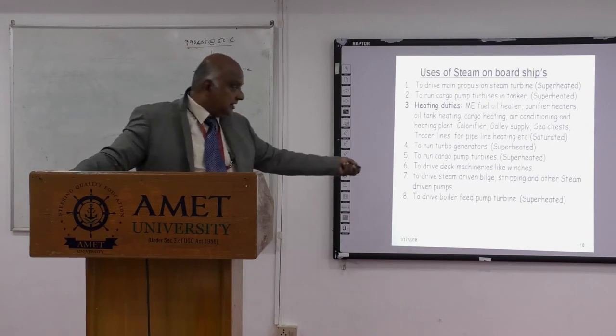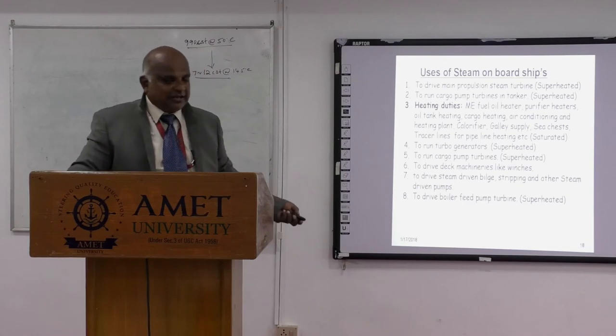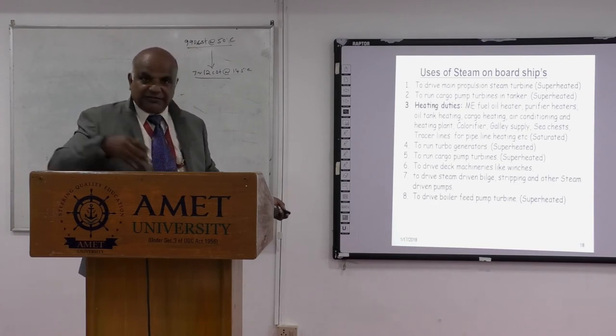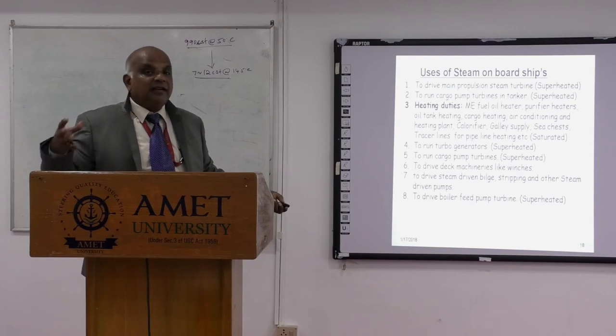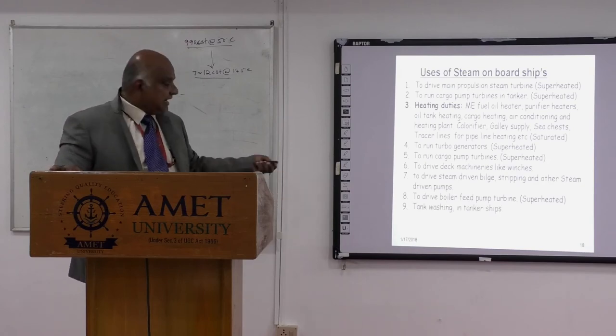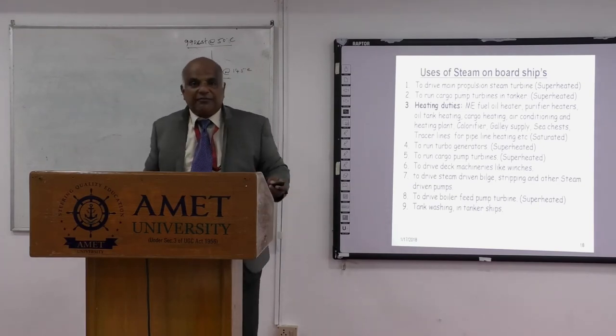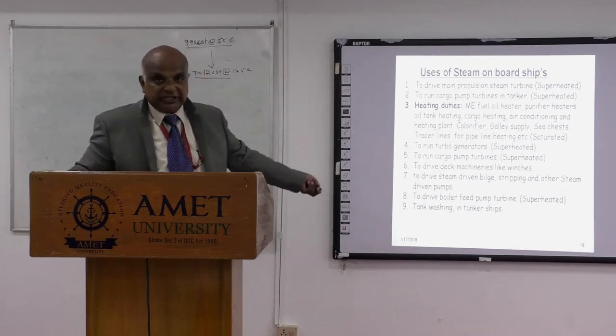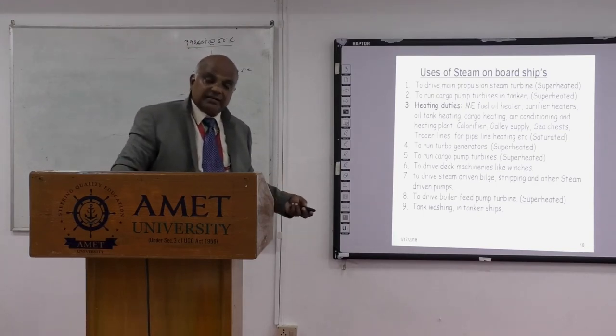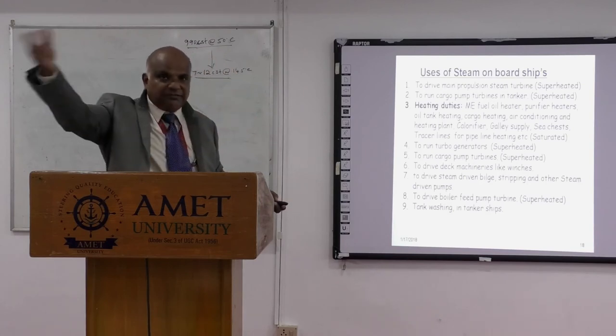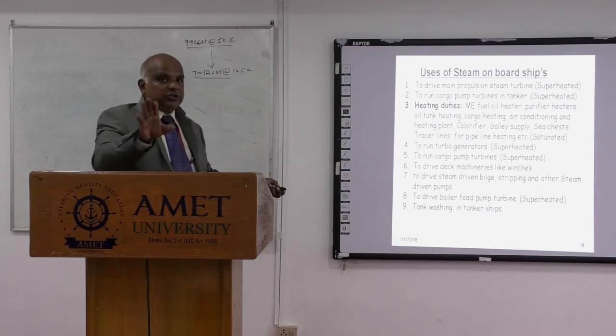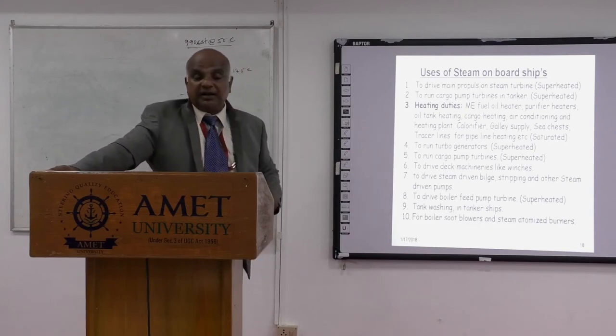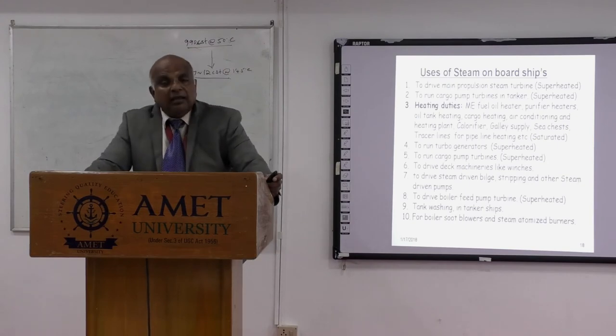To drive the boiler feed pump turbine — superheated steam at 435 degrees centigrade drives a turbine-coupled centrifugal feed water pump. Also, tank washing in tanker ships — after discharging cargo, steam is used to wash cargo tanks under controlled conditions with the inert gas system before loading a different grade of cargo.